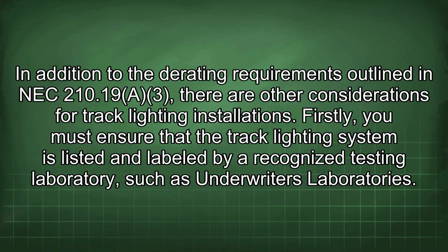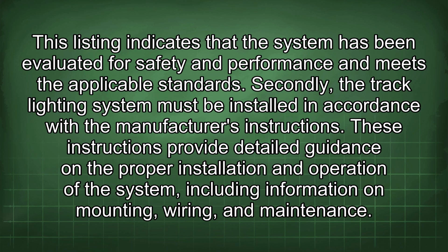In addition to the derating requirements outlined in NEC 210.19 A3, there are other considerations for track lighting installations. Firstly, you must ensure that the track lighting system is listed and labeled by a recognized testing laboratory, such as Underwriters' Laboratories. This listing indicates that the system has been evaluated for safety and performance and meets the applicable standards. Secondly, the track lighting system must be installed in accordance with the manufacturer's instructions.